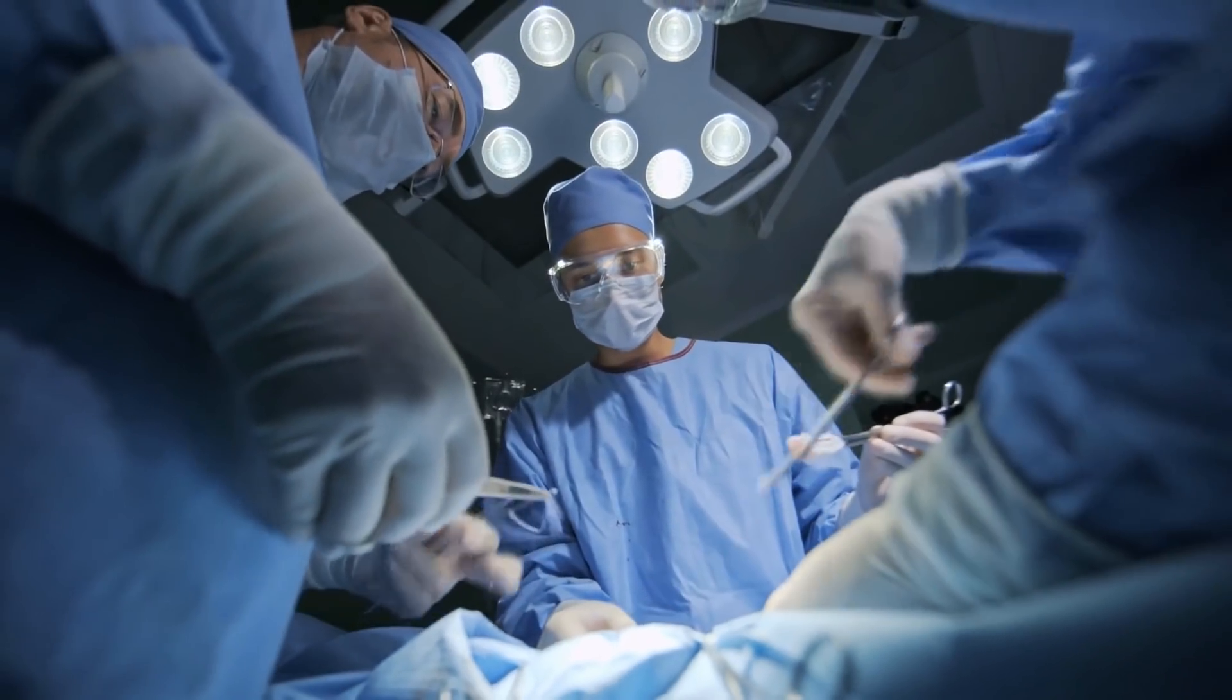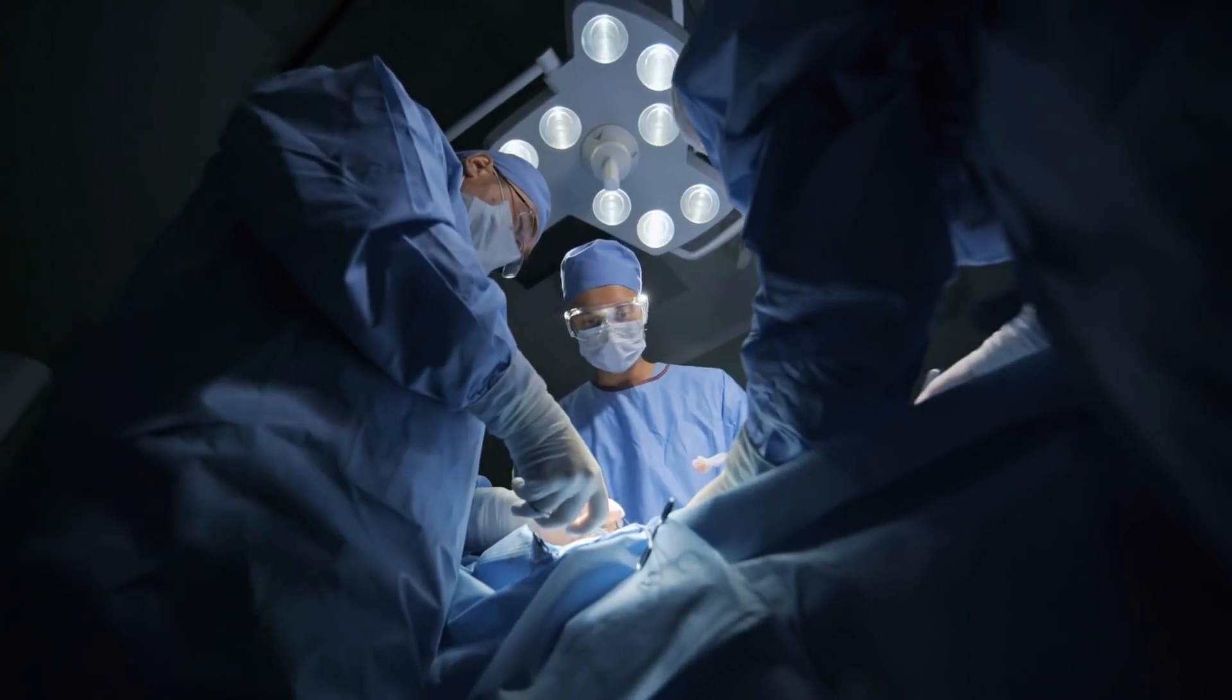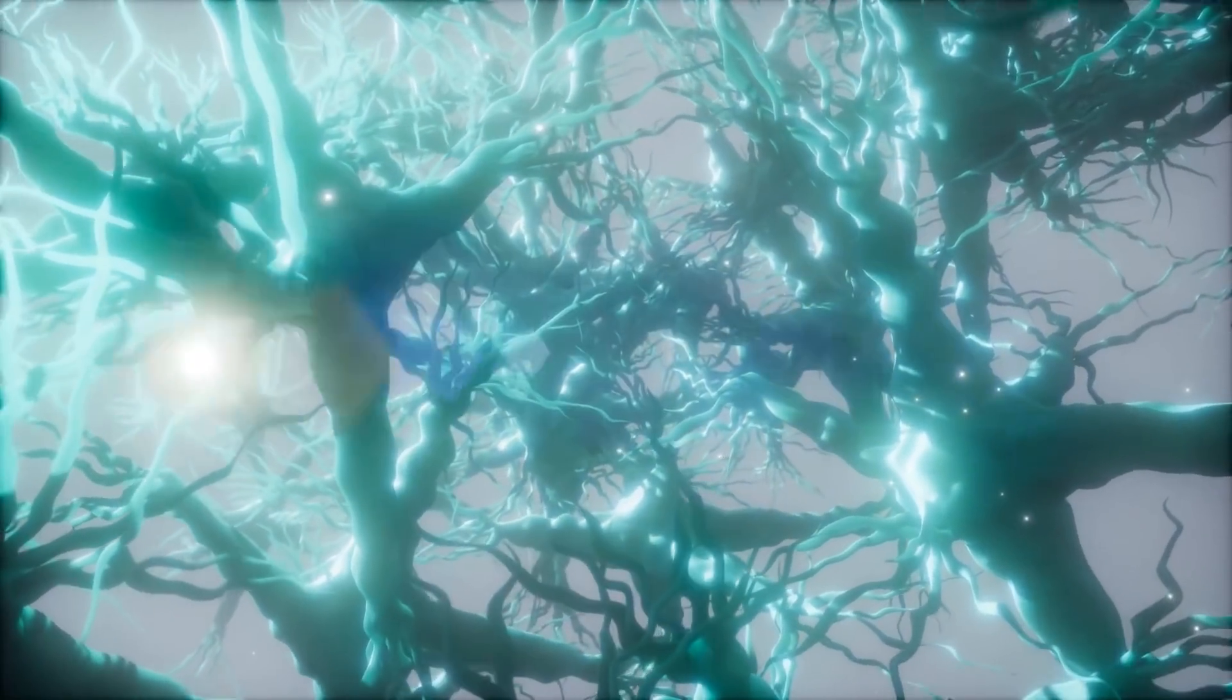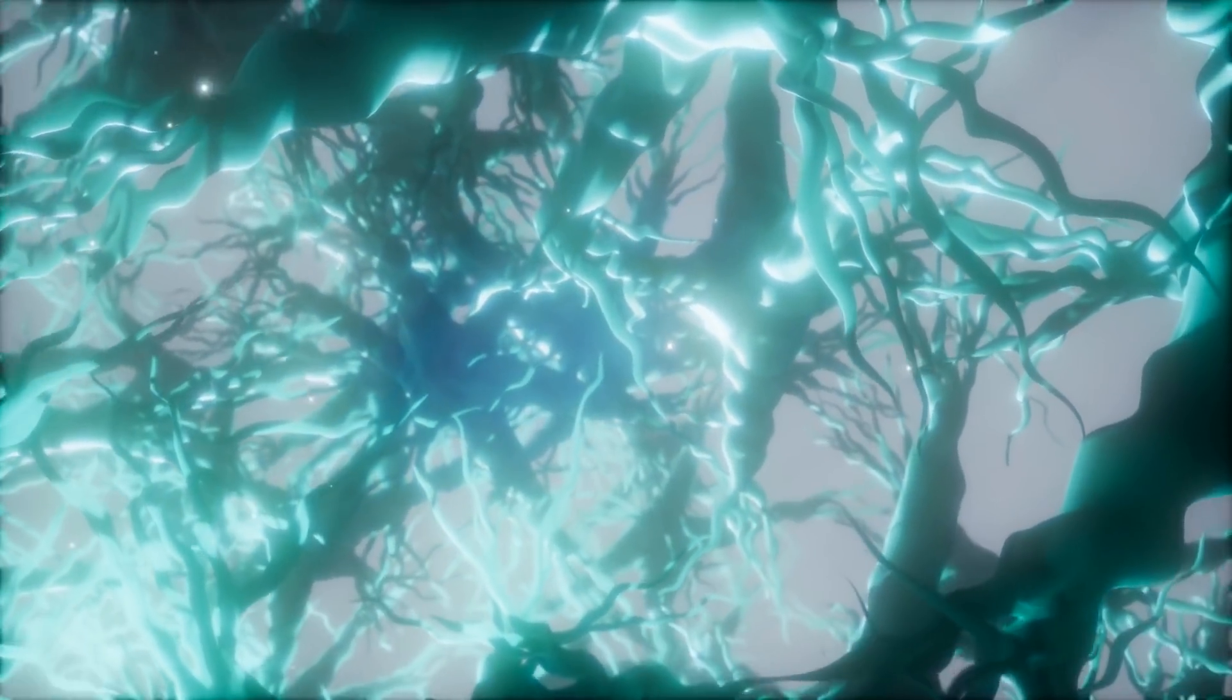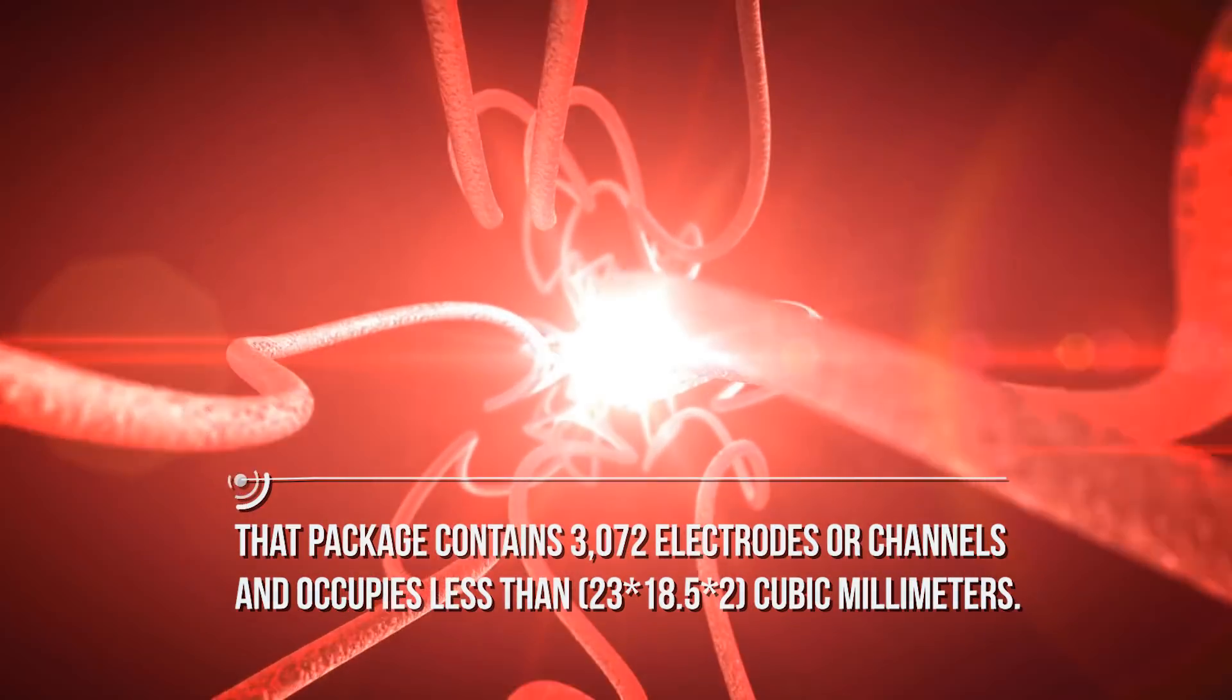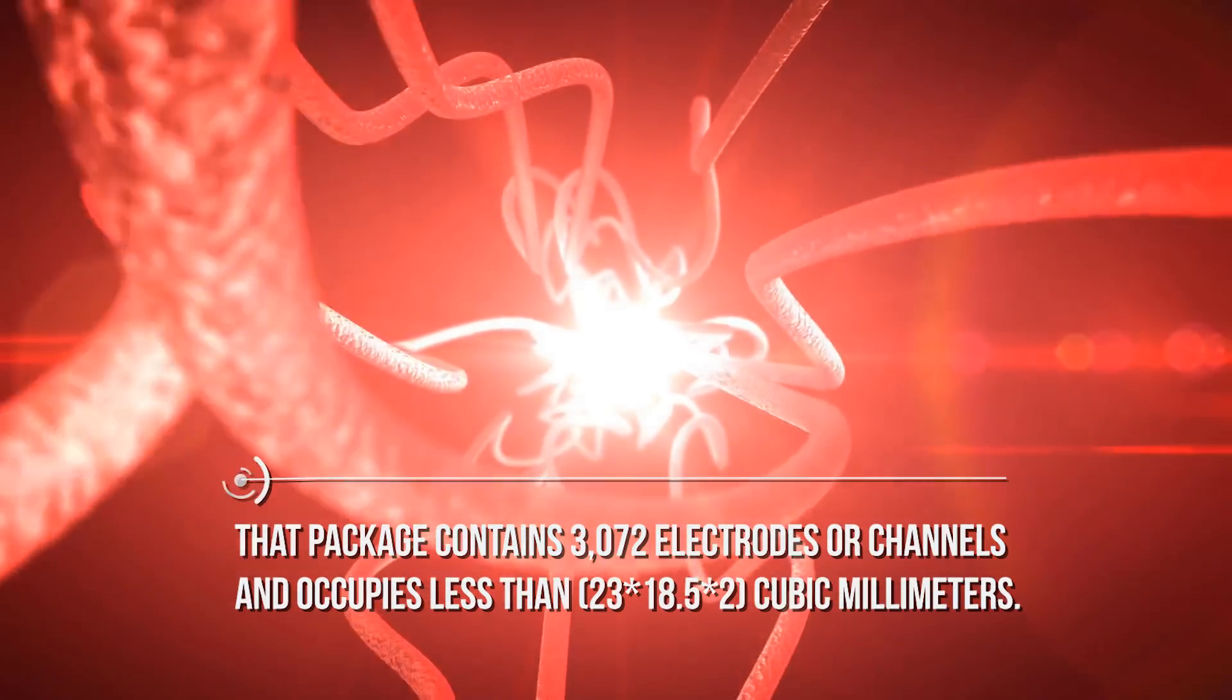Neuralink's approach to brain-machine interfaces technology has unprecedented packaging density and scalability in a clinically relevant package, where the electrode array is packaged into a small implantable device containing custom low-power onboard chips for amplification and digitalization. That package contains 3,072 electrodes and occupies less than 23 x 18.5 x 2 cubic millimeters.